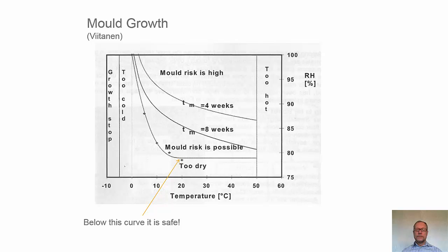So it's somewhere below 77 to 80% relative humidity, for temperatures around 20 and higher. When it's colder, between 0 and 20, we can accept high relative humidities in the construction because the mold doesn't want to establish when it's that cold. It thrives when it's warm.